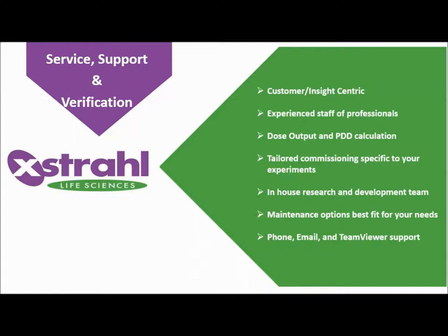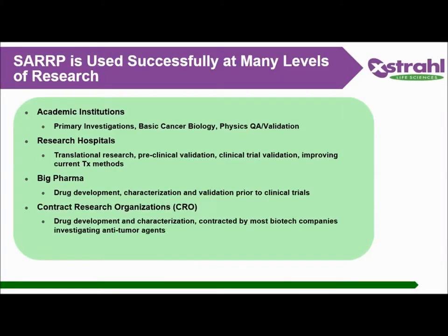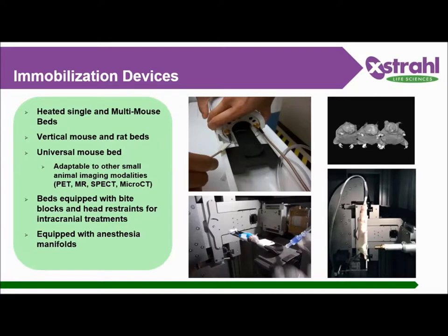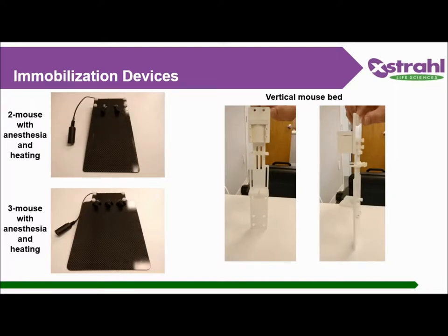All our systems are commissioned in-house — I personally take care of the commissioning. The SARRP is used at many levels: university, research, hospital, big pharma, and contract research organizations. We have many different animal beds available: one, two, and three mouse beds, rat or mouse vertical beds, a universal bed that can go easily into an MR and back onto the SARRP — keeping the animal position for cleaner image fusion — as well as heated beds to maintain animal body temperature while under anesthesia, with integrated isoflurane masks. Vertical options are also available.